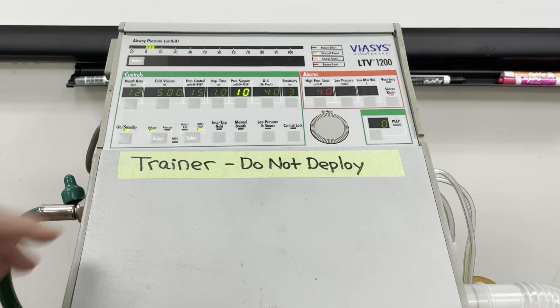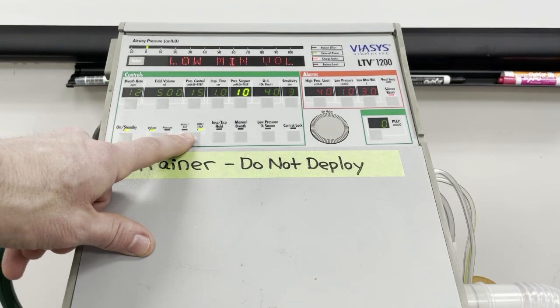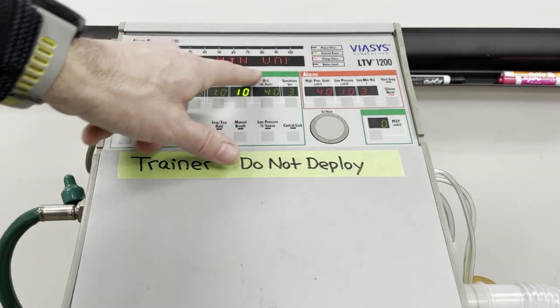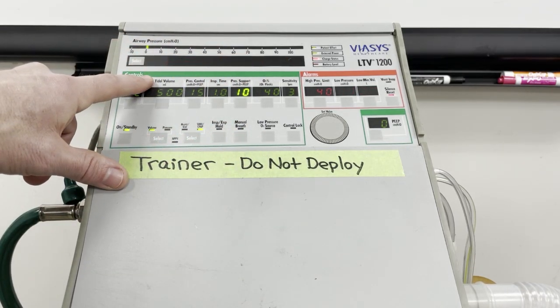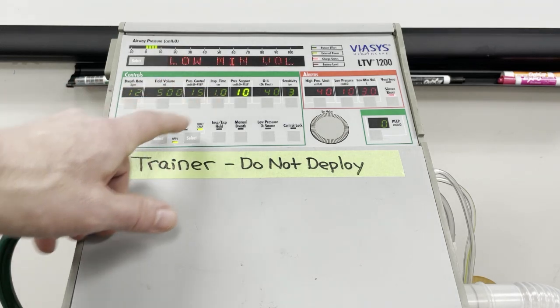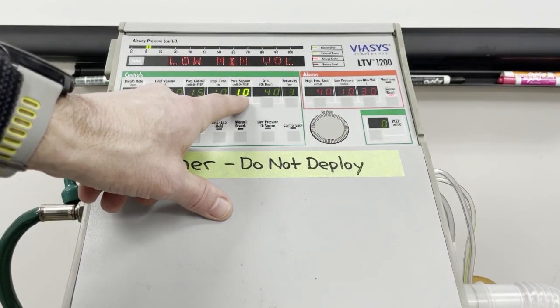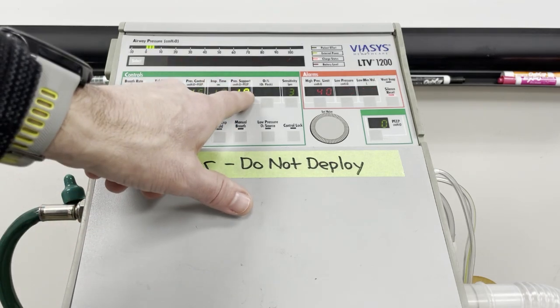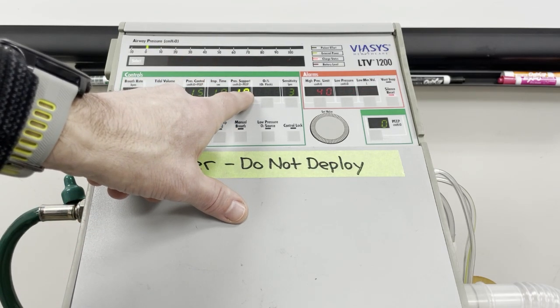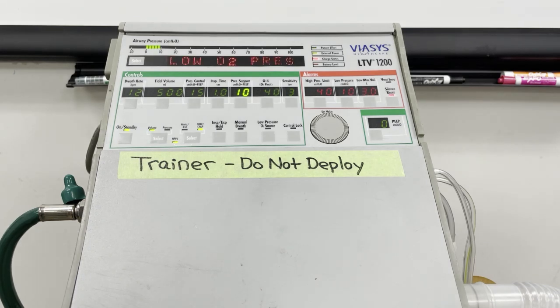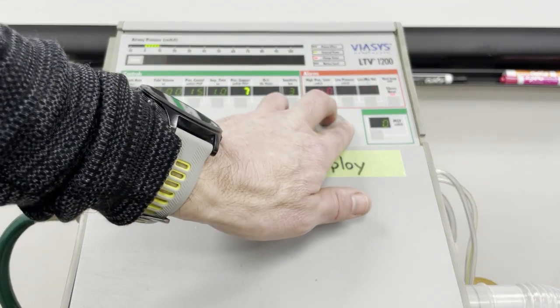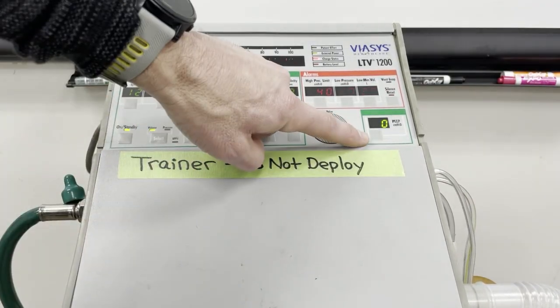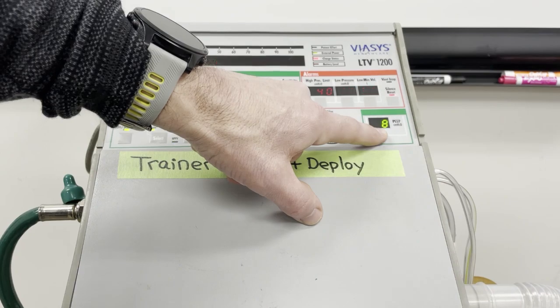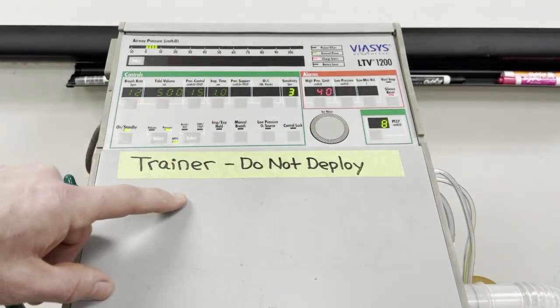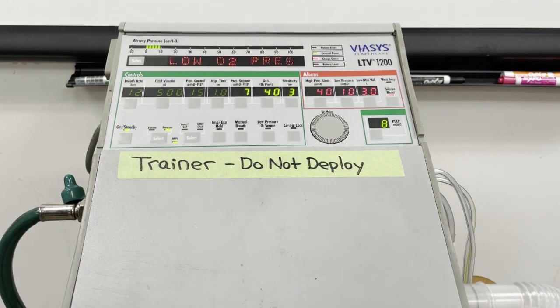Next, we toggle the mode button until we reach NPPV. Like I said earlier, you won't see the prompts because of the alarm message. You will notice that the other settings have dimmed out and only pressure support is lit up. Don't push the button until you have dialed it to the correct value. When you push it, the value is accepted and now PEEP is lit up. After that's been set, push the button to accept and the vent is now in NPPV mode.